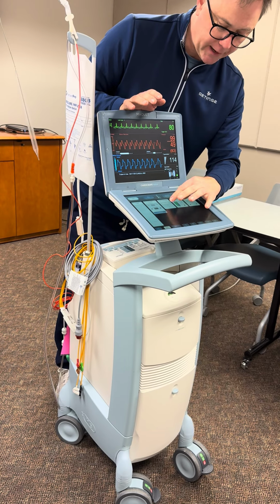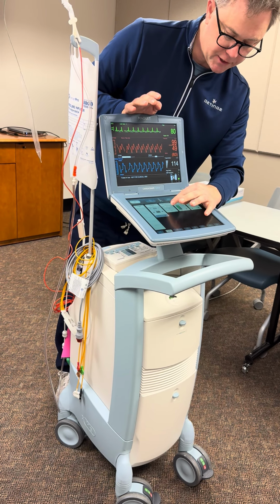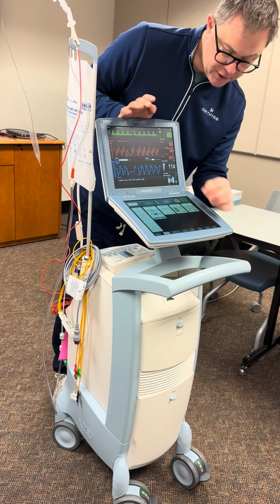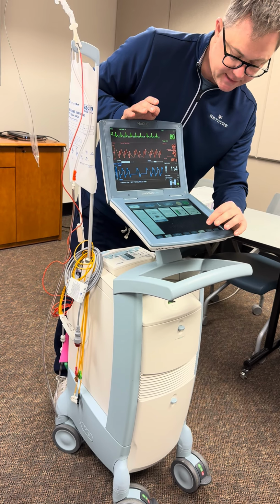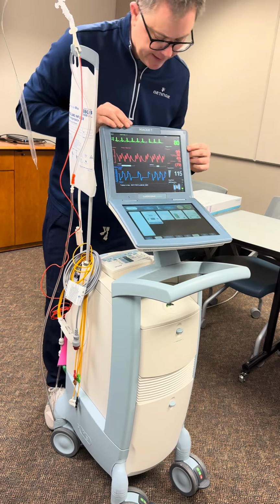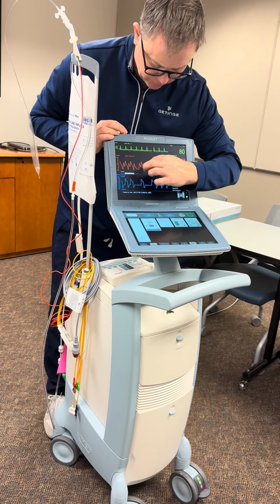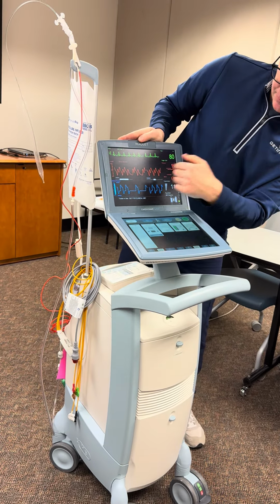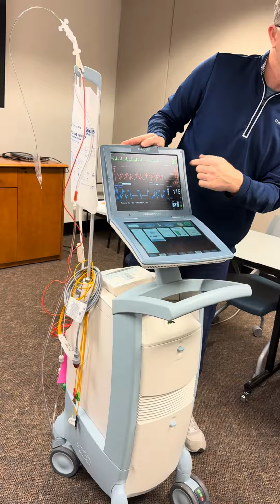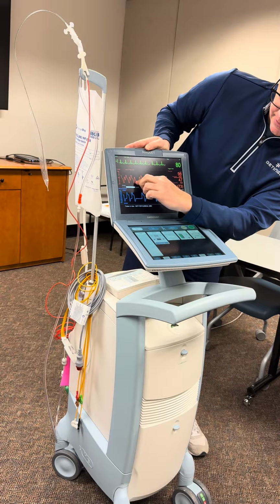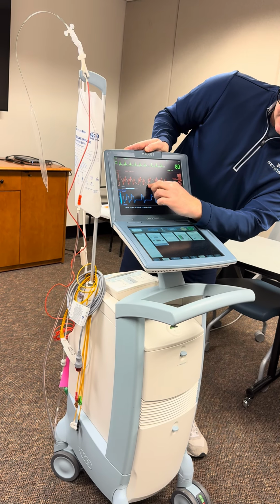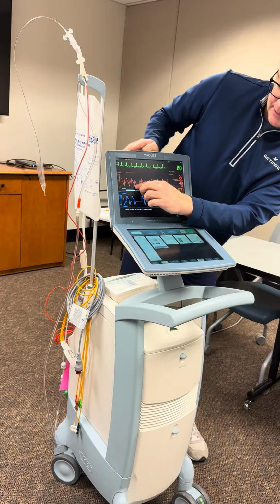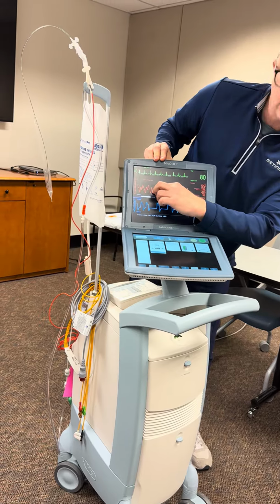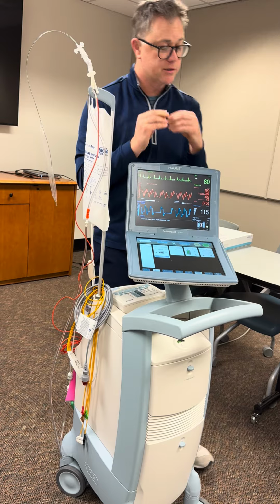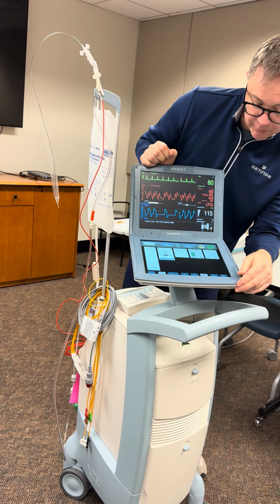And I don't mean to jump around here, but we're in 1-to-1 right now, just going over that waveform. When I put the patient into 1-to-2, if I were to freeze this display, we've got their native arterial pressure, and then we've got this. So every other beat right here is getting support. Every other beat's getting a balloon. We've got an unassisted beat, assisted beat, unassisted beat, assisted. So on that unassisted arterial pressure waveform, the dicrotic notch is where that aortic valve is closing, and that's where we want this balloon inflating.